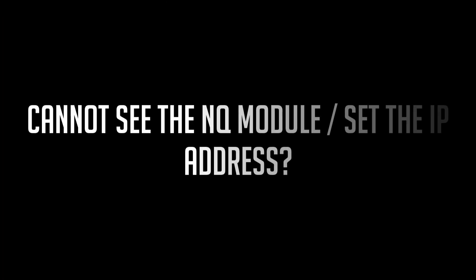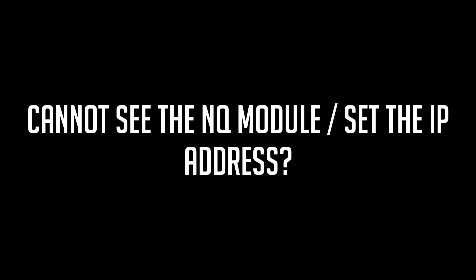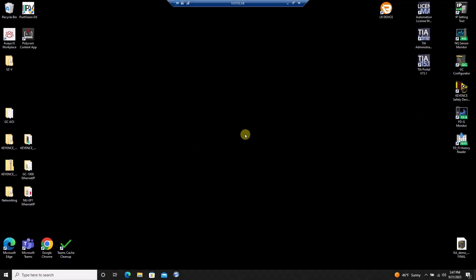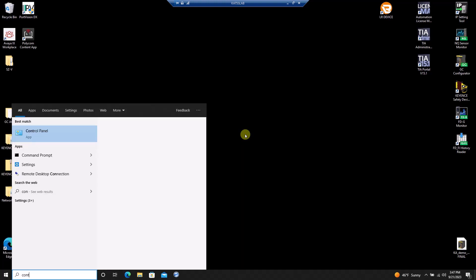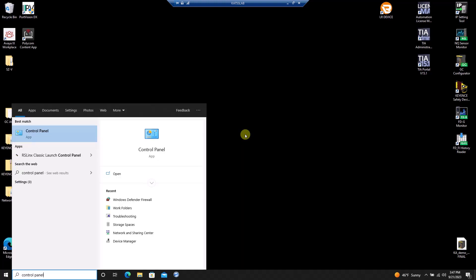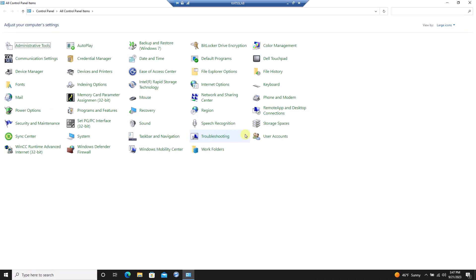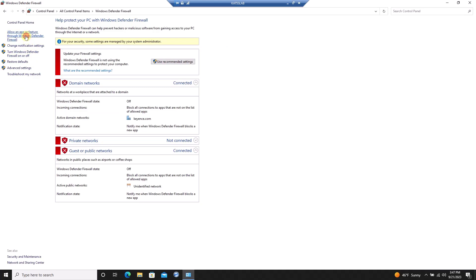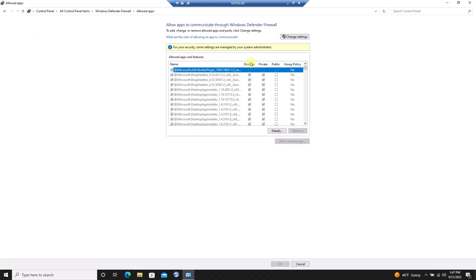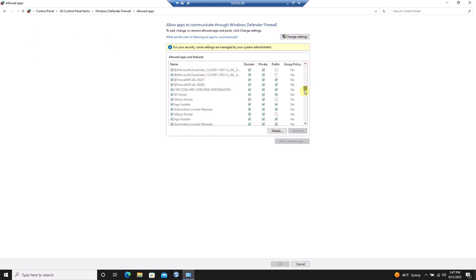If you didn't see the NQ module populate in the IP setting tool, I recommend checking your firewall settings. Often the IP setting tool needs to be granted permission through the firewall on your computer. Enter the control panel, then select Windows Defender Firewall, then select Allow an app through firewall. Look for the IP setting tool in the list that appears.